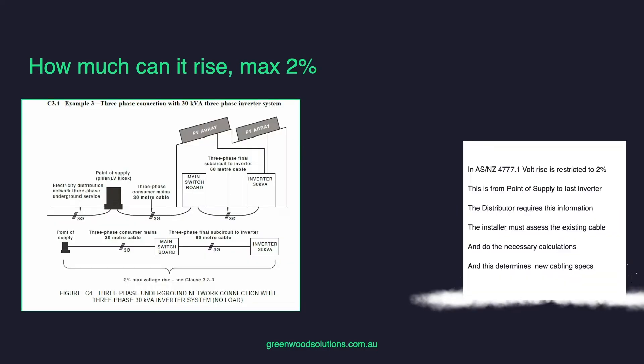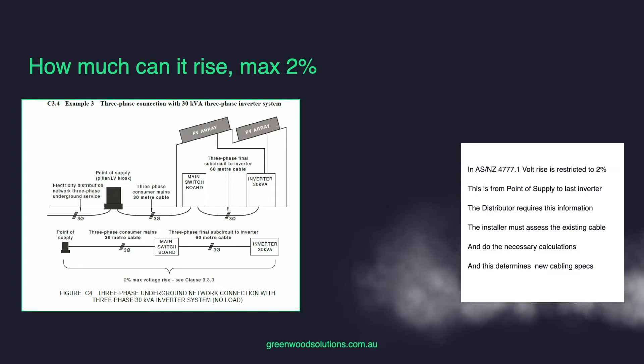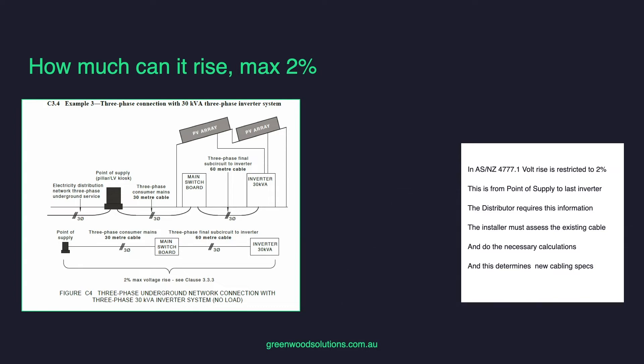In AS4777, volt rise is restricted to 2%, as you can see in the diagram. This is from the point of supply to the last inverter, and the distributor requires this information. The installer must assess the existing cable or cables, do the necessary calculations, and then this determines the new cabling specs.